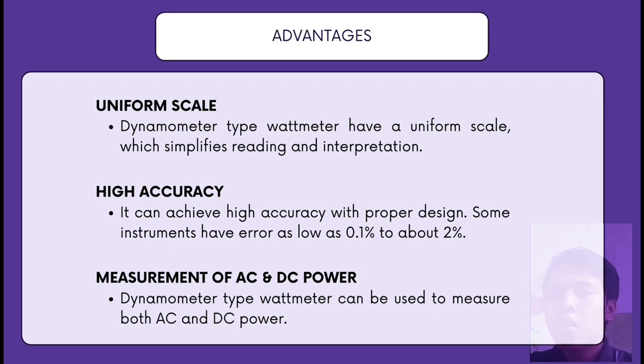So, the first advantage is a uniform scale. Dynamometer type wattmeters have a uniform scale, which simplifies reading and interpretation. Next, high accuracy. It can achieve high accuracy with proper design. Some instruments have errors as low as 0.1% to about 2%. Next is measurement of AC and DC power. Dynamometer type wattmeters can be used to measure both AC and DC power.